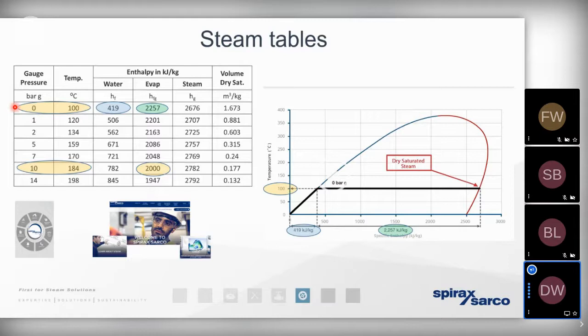So problems caused by wet steam. First of all, wet steam is far more likely to give up its energy to the distribution pipework and condense. So we can start off by generating 10,000 kilograms per hour of steam, but we could be losing 500 kilograms per hour to the pipework, meaning we get a reduced mass of steam finding its way to all of those processes. It's an inefficiency. That condensate needs to be removed. So the wetter the steam, the more condensate, the more steam traps we need to engineer and maintain. If we've got condensate that exists in the distribution pipework, we're more at risk of corroding pipework and other ancillaries. We're more at risk of erosion, and we're more at risk of water hammer, all of which are mechanical maintenance issues we'll need to contend with.